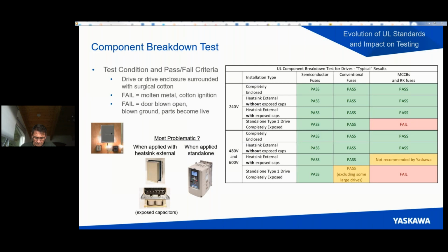Even the 240 volt drive won't survive this, because besides the shorted capacitor test, there's also a shorted rectifier test that won't pass for this combination. Now, looking at the 480 volt and 600 volt cases, we can see there are a few more restrictions, and that's because of what happens when we do that shorted capacitor test on the 480 volt and 600 volt class drives. Notice that for the case of external heatsink for drives with exposed capacitors, that's the yellow cell in the rightmost column.